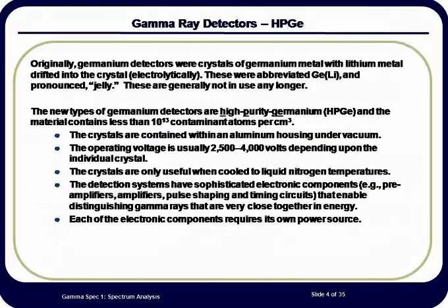There are 2 types of germanium detectors. The older version was a lithium-drifted crystal of purified germanium. It began to be phased out in the early 1980s when the production of high-purity germanium became a more routine practice. The germanium detectors also detect gamma rays via the photoelectric effect, but these crystals are cooled to liquid nitrogen temperatures and have voltages applied to the crystals of about 2500 to 4000 volts. In the germanium detectors, the photoelectron is accelerated in the voltage field applied to the crystal, and it ultimately produces a pulse at the detector's preamplifier that is proportional to the original gamma ray energy.